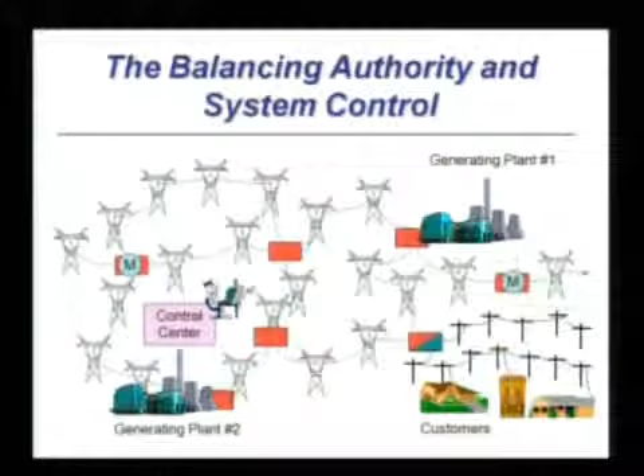But in all seriousness, a control area is just a metered, electrically metered physical boundary. On his system, he's interconnected over here on the east with a meter that defines that interconnection, and interconnected over here on the west, again with a metered boundary. Everything within those metered boundaries is his control area - he's got customers on distribution, generating plants, transmission, all of which he has to maintain and operate, primarily to instantaneously balance supply and demand.